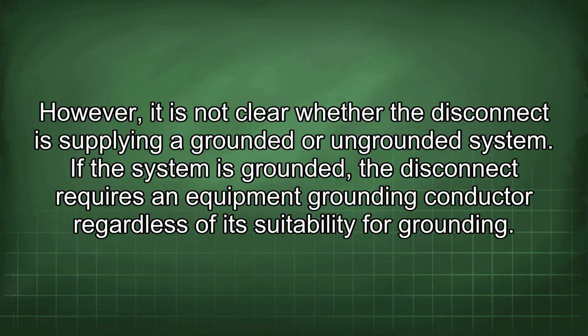However, it is not clear whether the disconnect is supplying a grounded or ungrounded system. If the system is grounded, the disconnect requires an equipment grounding conductor regardless of its suitability for grounding.